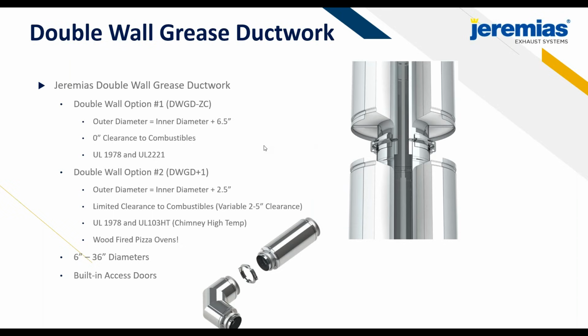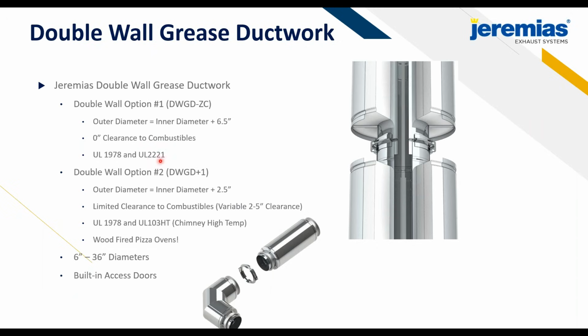It's very easily installed. All the parts and pieces are delivered with these, as well as the supports, as I mentioned. With double wall, we can also go to this UL 2221 listing, and that is a zero clearance to combustibles. So it is actually its own chase, and you don't need a dedicated chase if you have a UL 2221 listing. It does get quite big though, to be honest, because you have your inner diameter plus 6.5 inches on also, so it is quite big, but you don't need a dedicated chase for this one.